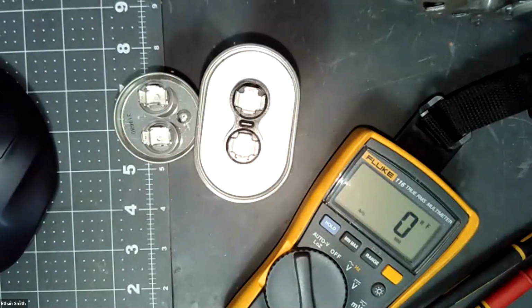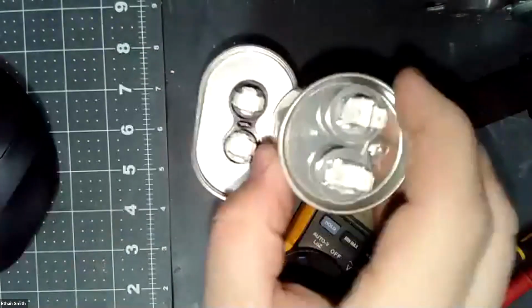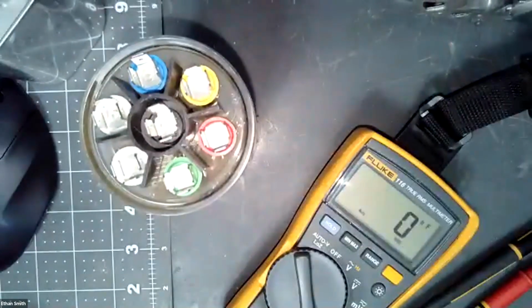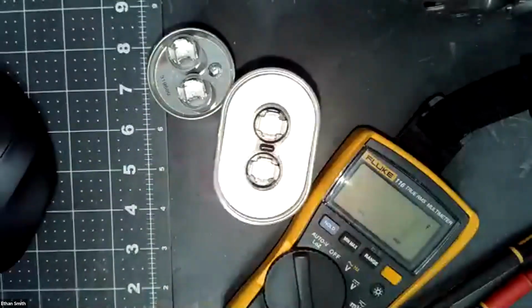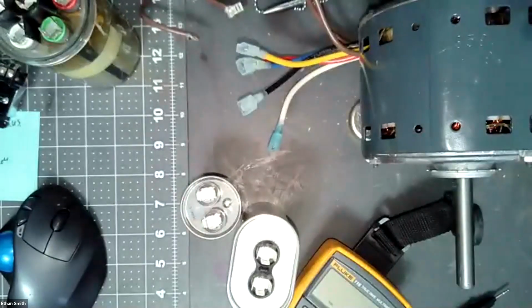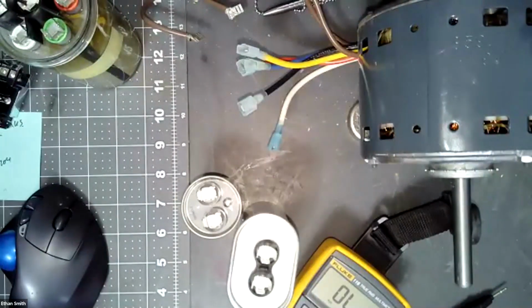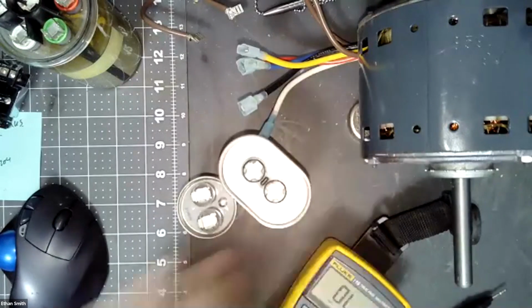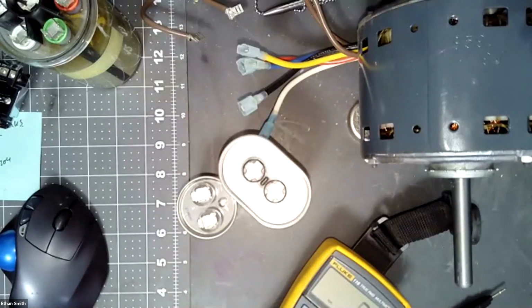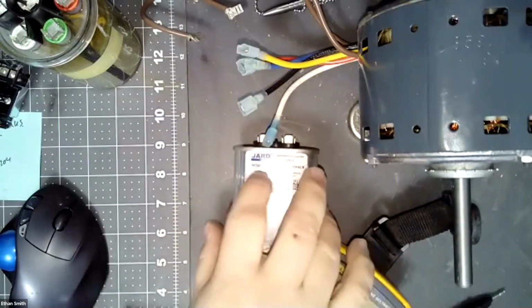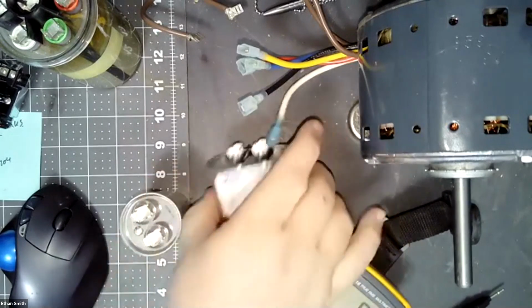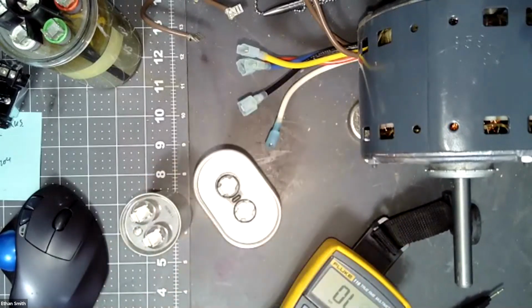I'd prefer to have a capacitor of the right size, or one of these in an air conditioner, versus trying to find a place to mount 2 of those. But sometimes it's Friday night and the stores are closed, and this is what you have to do to get them running. So you could certainly use those jumpers, and I wouldn't have any problems with longevity as long as you're matching your capacitance and your insulation value with those.